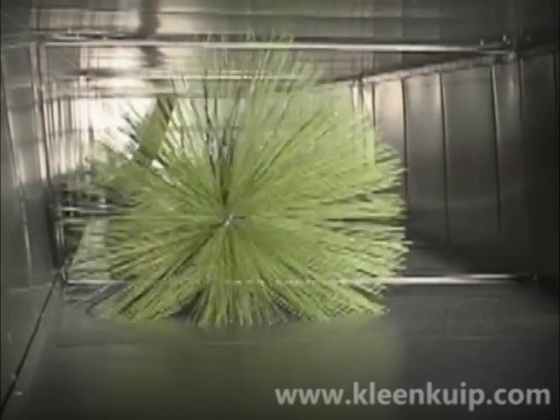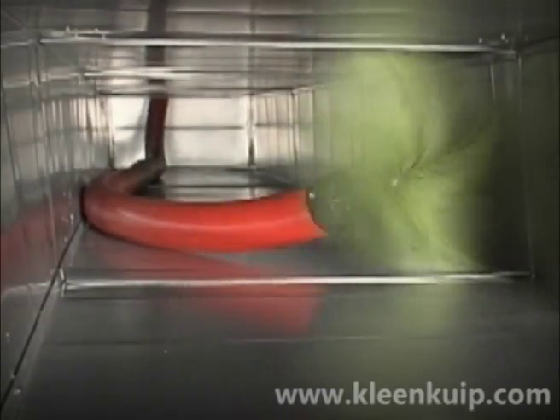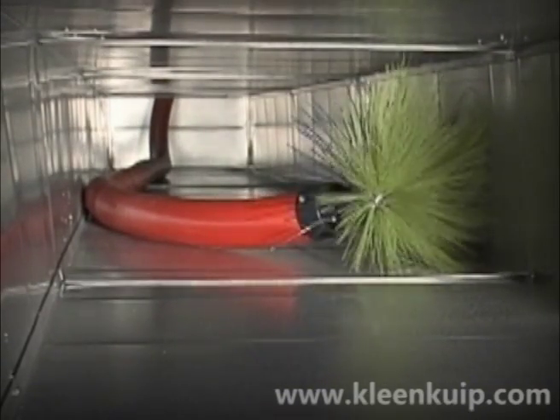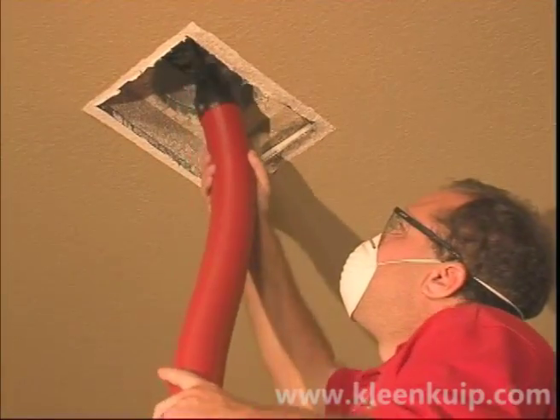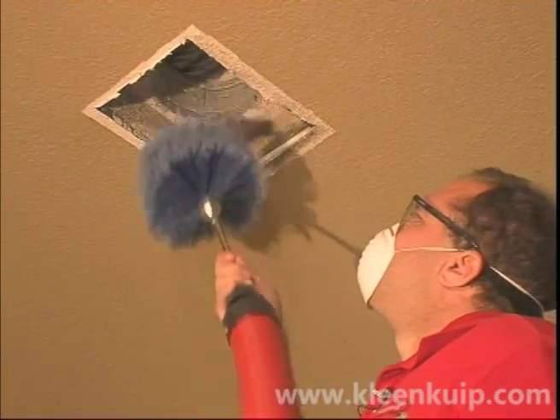Reverse the brush rotation to cause the brush to travel towards the other side of the duct. Pull the brush back about 6 inches and then reverse the direction again. Repeat as needed to clean the length of the duct. Prior to removing the brush from any air duct, make sure you turn off the brush rotation.